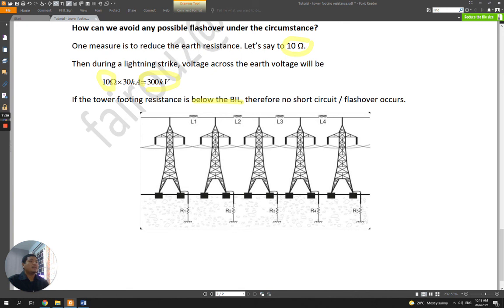So you can see that it is important to reduce the value of tower footing resistance. Every tower has its own footing resistance, so it is important to make sure that each resistance is below the required limit, so that it will not cause flashover to the system.